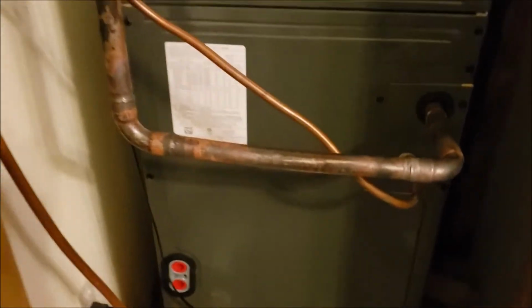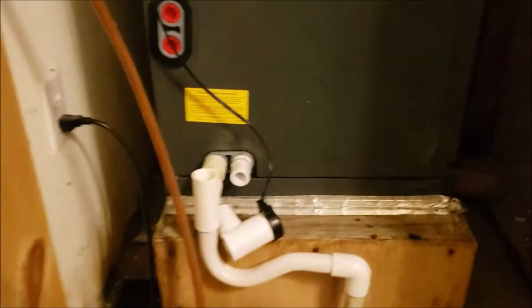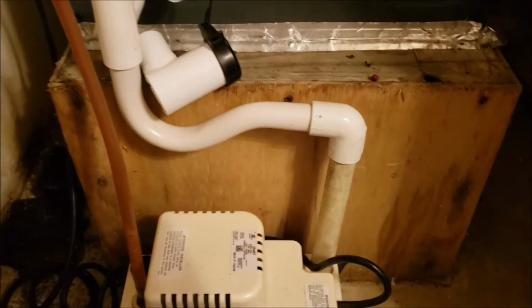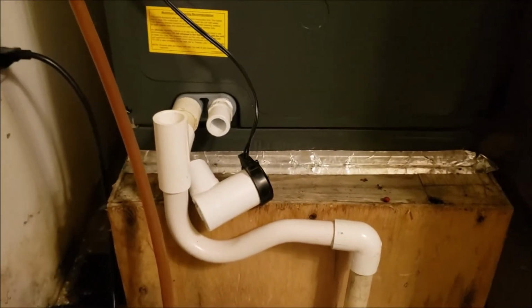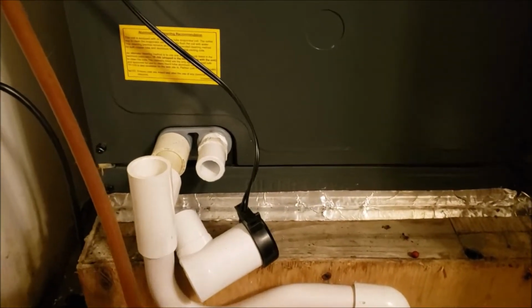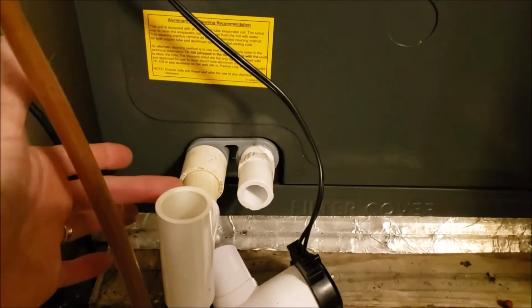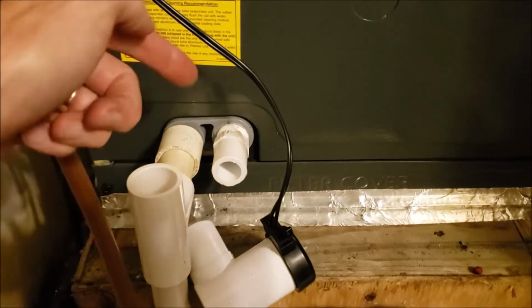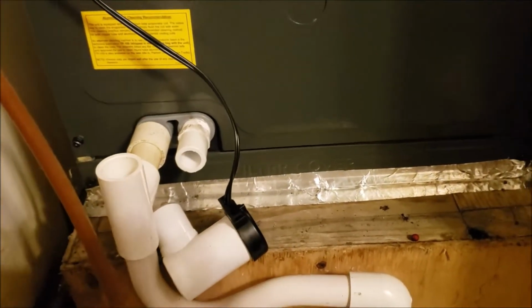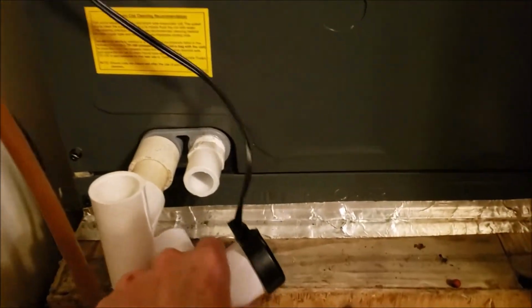I'm going to get the insulation on the suction line, hook up the drain lines, and add a little safety device. One thing I noticed I didn't like is that it's got a condensate pump, and this is in a basement. It'd be different if it were in a crawl space, but because we're in a basement, if the main drain clogs up, the overflow will just flow water right out all over the floor. So I'm going to add this little device.